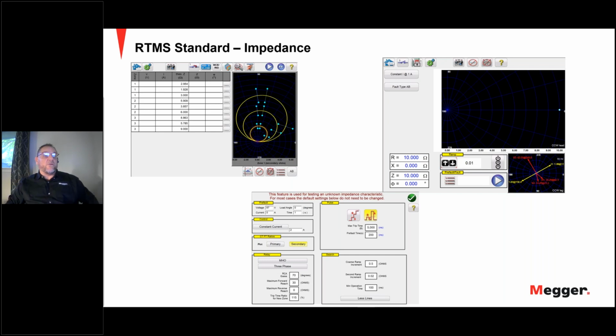Included in the COF tool is an impedance relay library, which provides a selection window containing relay-specific impedance characteristics listed by relay manufacturer and model type. Also in the COF is the Megger Characteristics Editor, a tool for creating impedance relay operating characteristics using a combination of lines, arcs, and/or Mho circles. These impedance characteristics created using the MCE can be imported into the click on fault test screen, tested, and results can be saved.